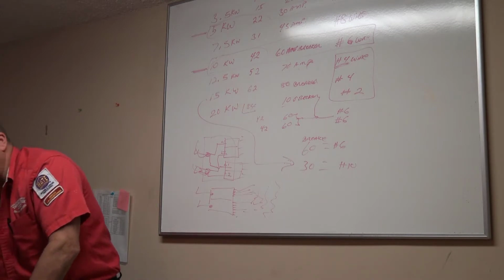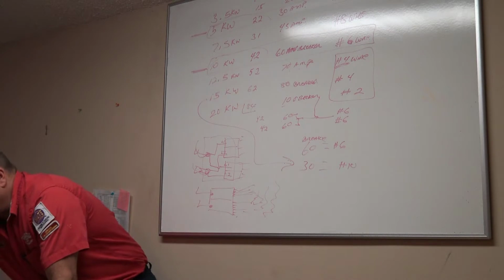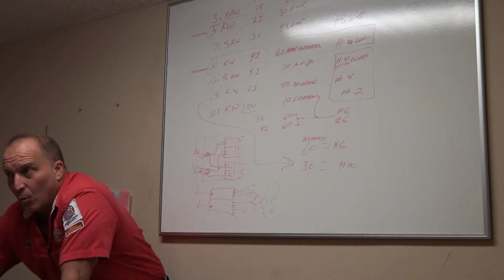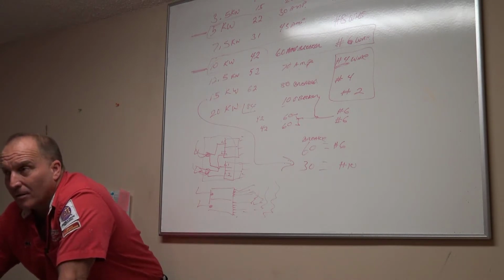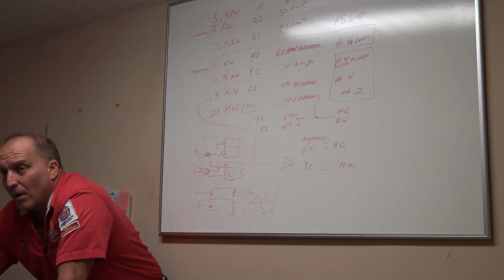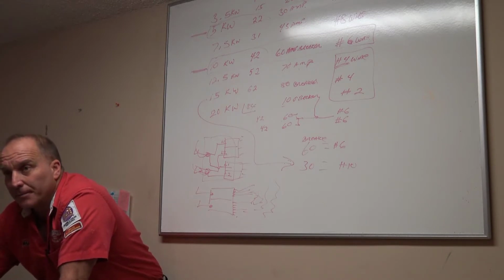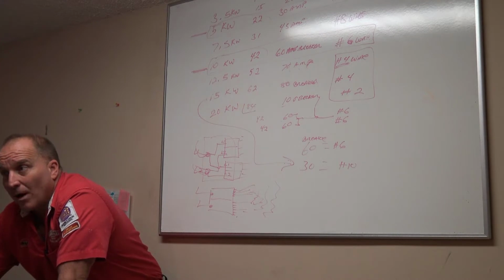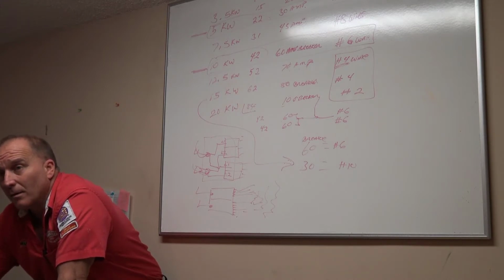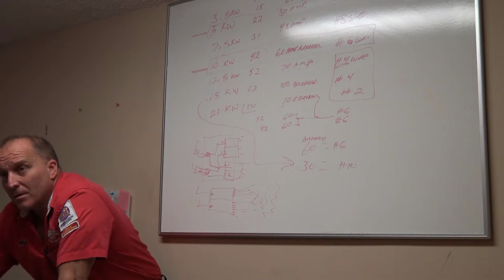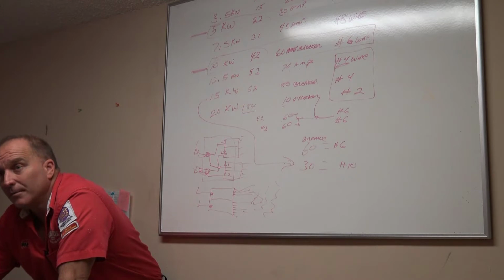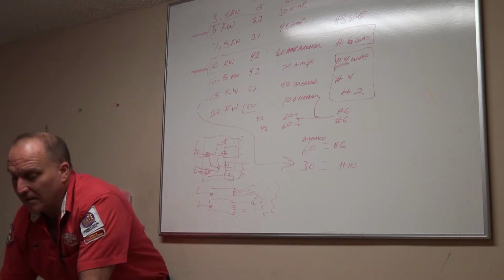So the customer may call you out because somebody was just there and they can't get it running, and whoever was there pulled all the wires off of the circuit board and now you have got to put them back on. And you go over there and you got wires just dangling down and nothing is attached to the circuit board. So what are you doing now? And guess what? On the door of the furnace, you can't actually read the wiring diagram. Now what are you gonna do? You can't see it. What are you gonna do now?